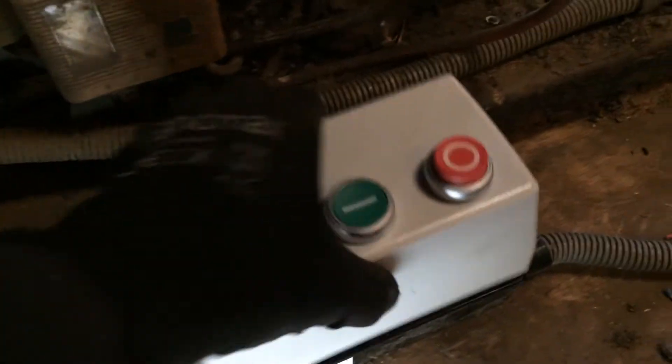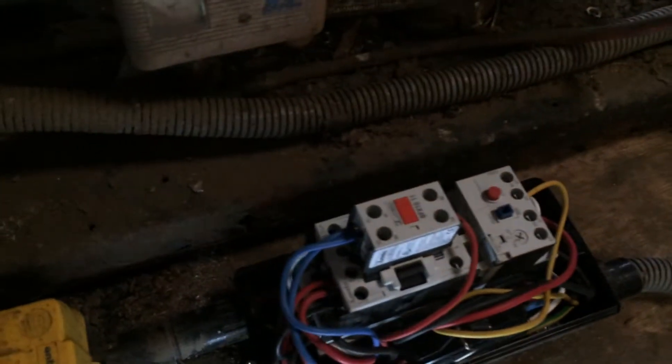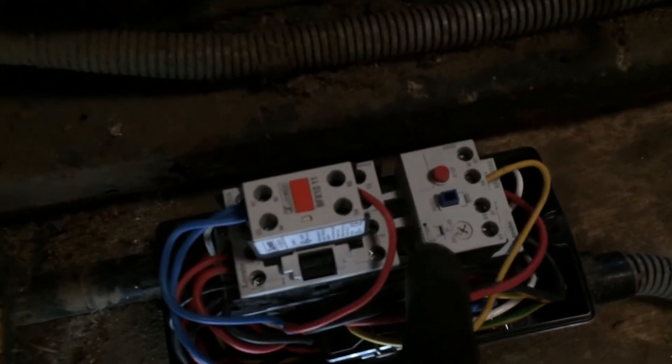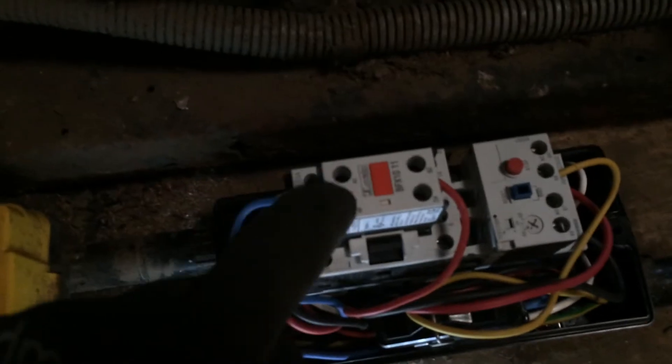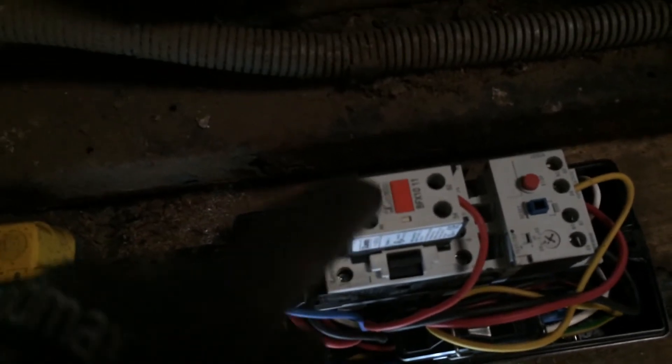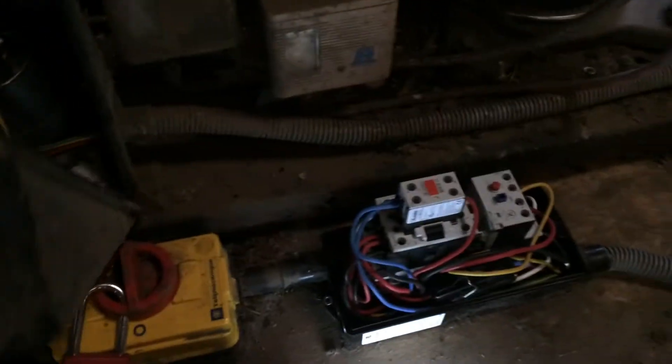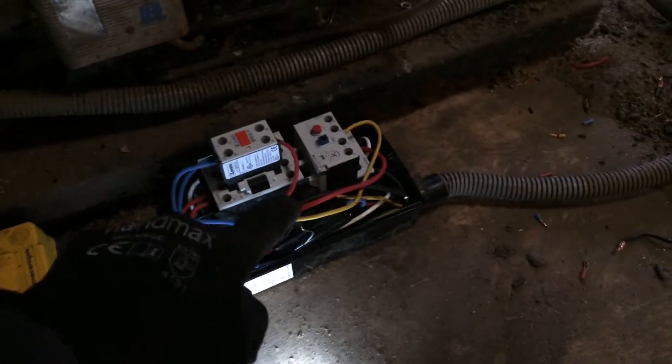Got the contactor, overloads and the auxiliary contact that is on when the contactor is off, and that powers up the crankcase heater. So we'll get all the lids put back on this and then we're going to put the amp probe on there and try it.